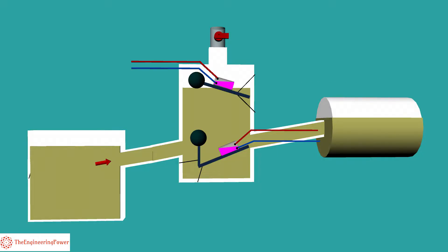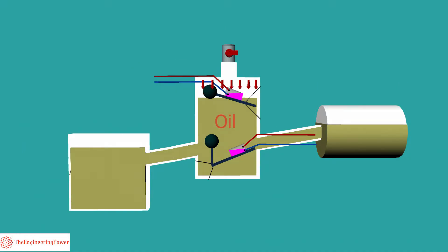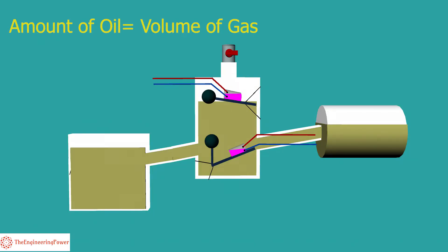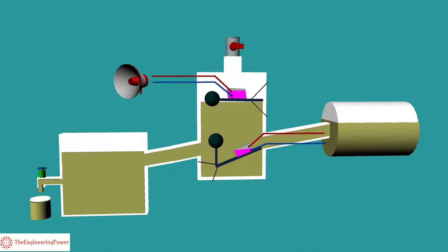These gases move towards the conservator tank through the connecting pipe and are collected in the chamber of the Buchholz relay. As these gases move upwards, they put pressure on the oil present inside the chamber and displace an amount of oil equal to the volume of the gas. This downward displacement of oil causes the attached float to tilt, resulting in closing the mercury switch which triggers the alarm circuit.